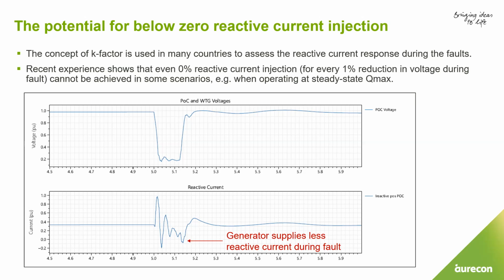With that note, once a fault occurs, say after a cycle or a cycle and a half, including measurement delays and everything, you expect the IBR to start injecting some reactive current and hold that response as far as possible. What is shown here is a response to a two-phase to ground unbalanced fault. It's a fairly severe fault, as you can see from the first trace. In the initial period the IBR provided a positive response, but it cannot hold this response, and it's very variable, which I will discuss in the next slide.